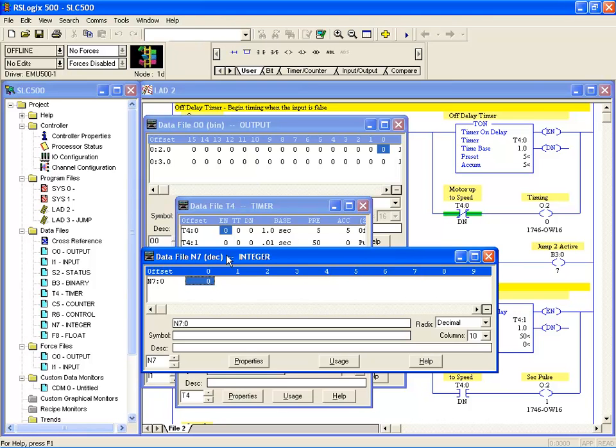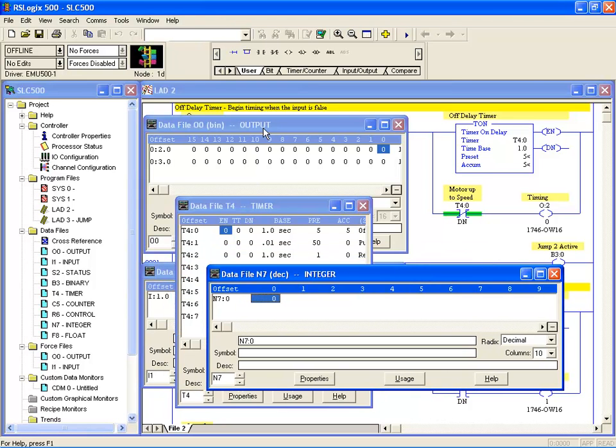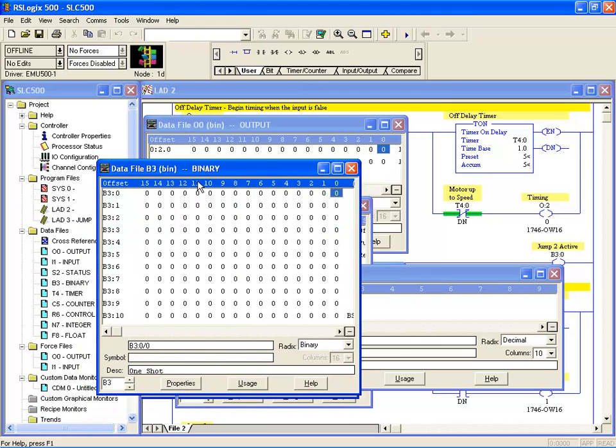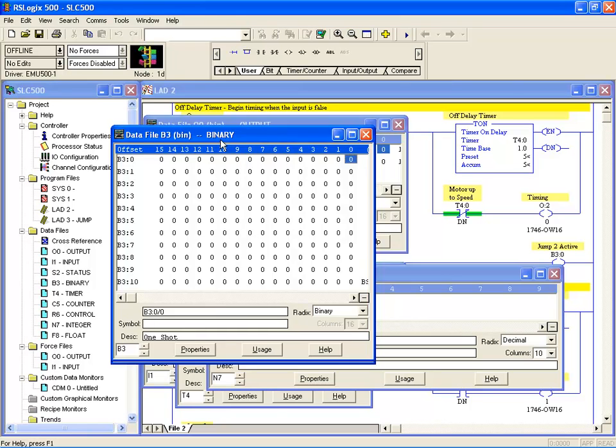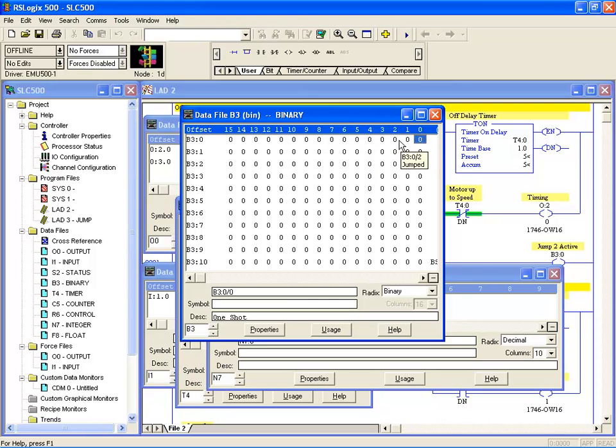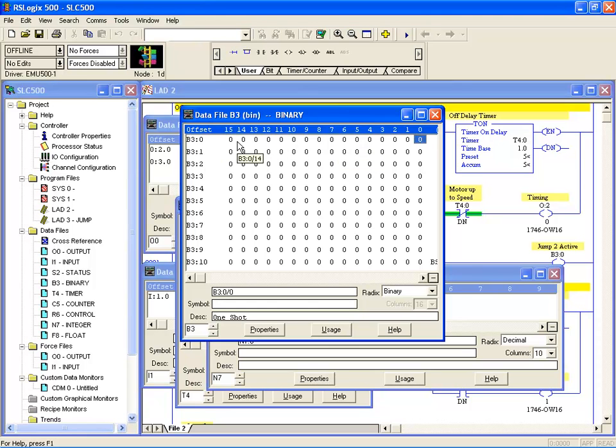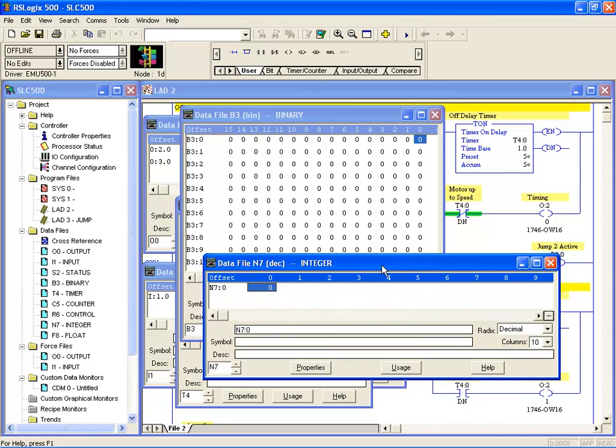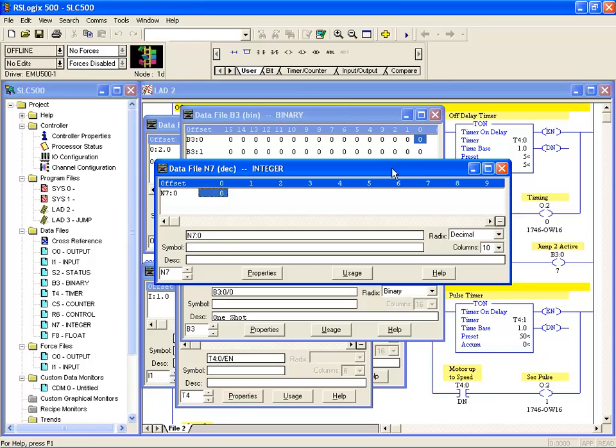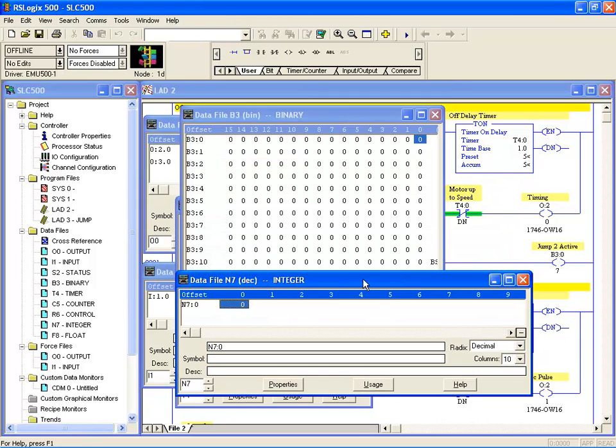Integer words will be something we venture further into in future lessons. The memory map includes input, output, timers, counters, and integers as well as binary files. They are all set aside in word format. Word format is 16 bits in the case of the SLC. So a word in an SLC PLC is 16 bits. In the binary file you can see laid out word 0, bit 0 through to bit 15, so there's a 16 bit word. In the integer files it's slightly different. The basic setup is a word, a 16 bit word which we can enter a large number into. So the radix or display is in decimal.